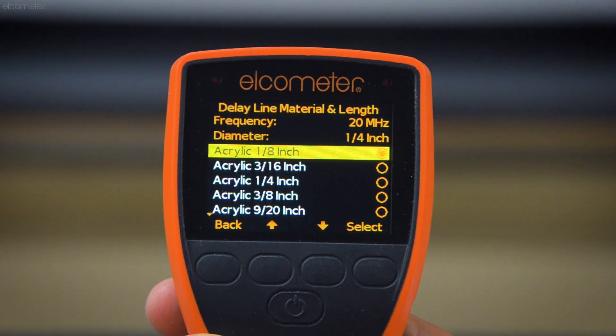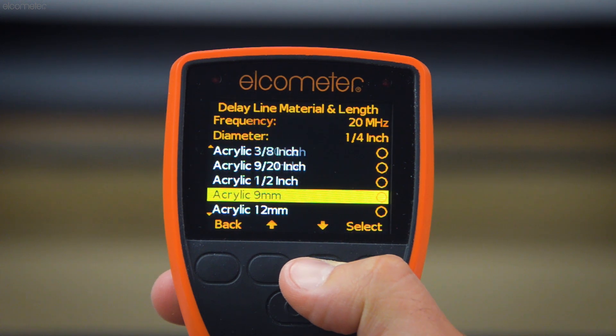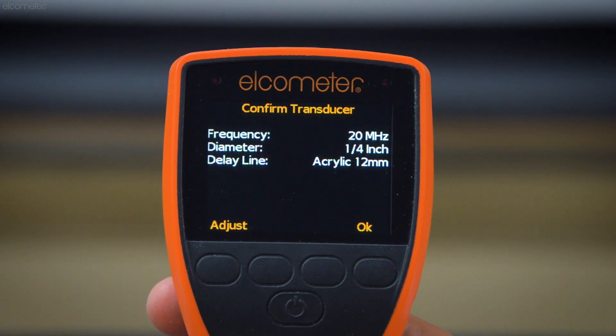You simply input the length and material of delay line before starting, and the gauge will subtract it from future measurements, leaving just the thickness of the material.